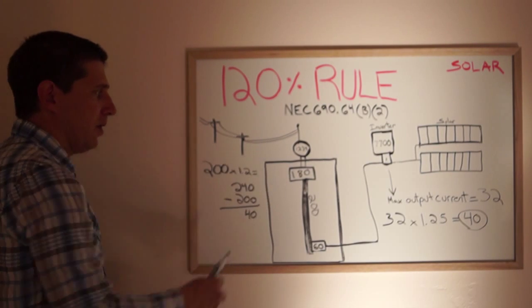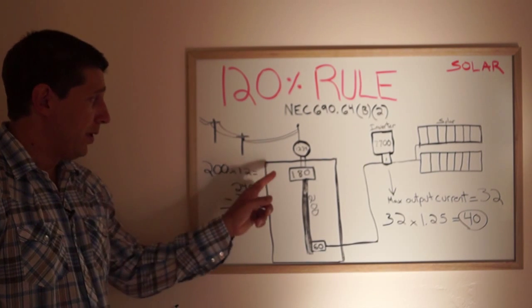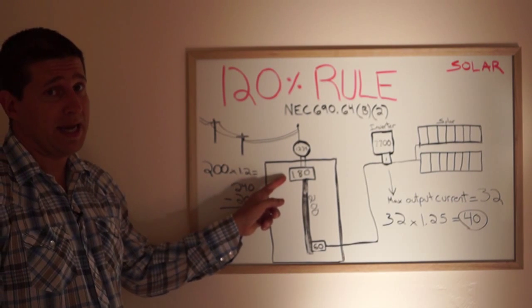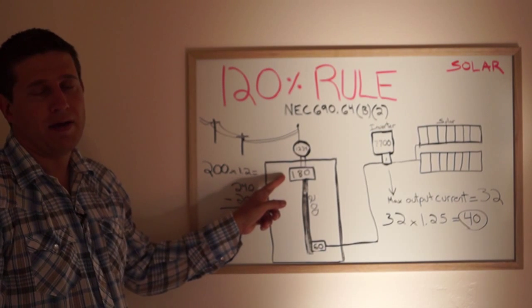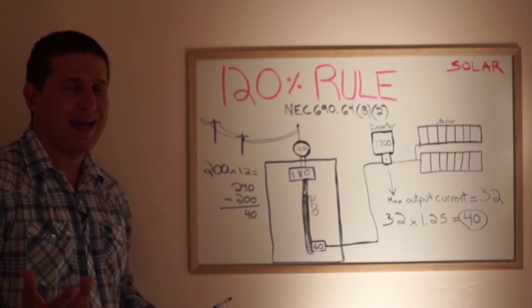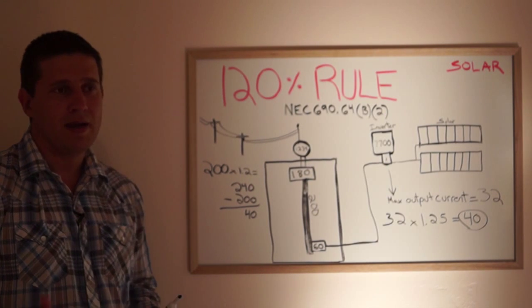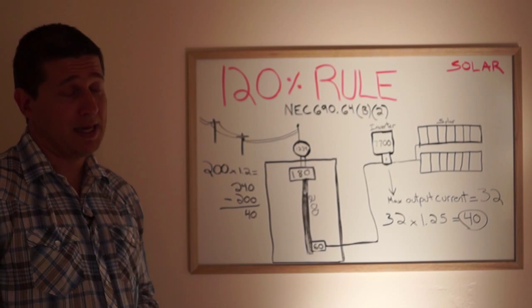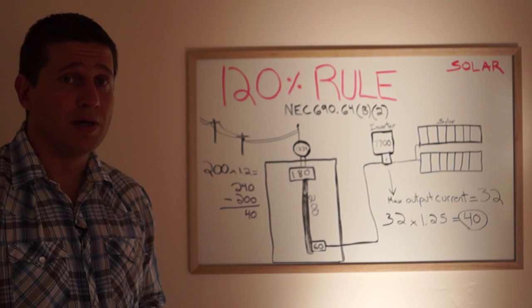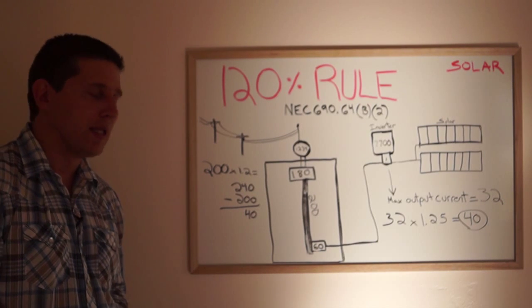However, we do have to be careful that at night time when the solar is not producing any power that we don't consume more than 180 amps. Or else we could be at fault that this 180 amp breaker might trip at times that we'd rather it not. Perhaps at 9 or 10 o'clock when a spa turns on. Maybe there's a sauna, electric vehicle.